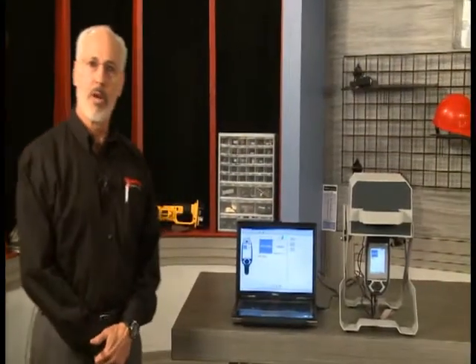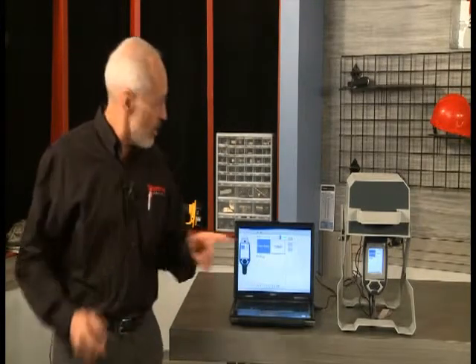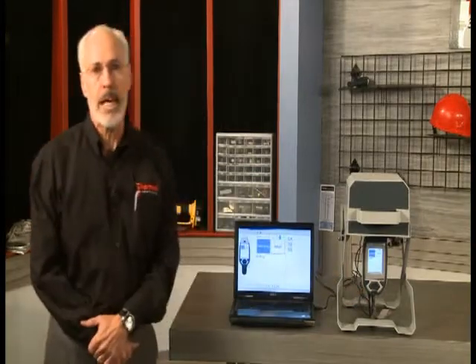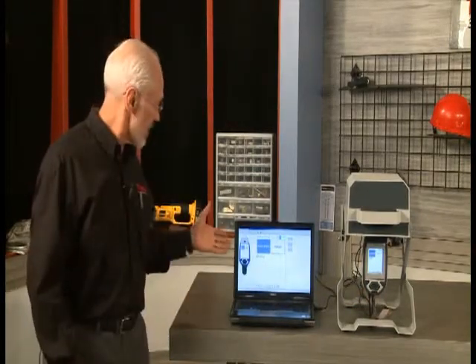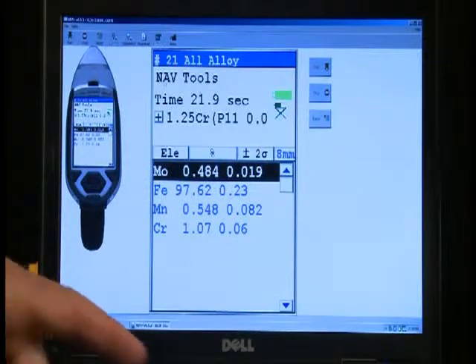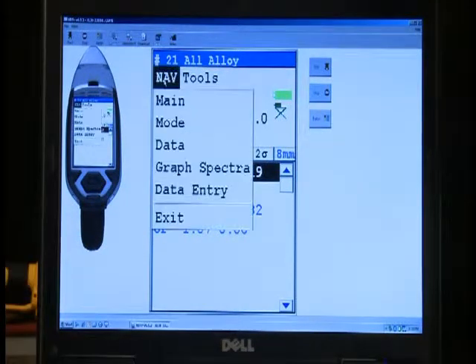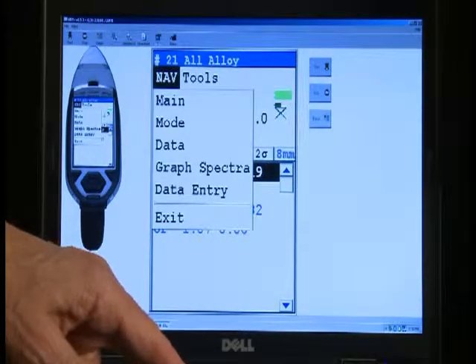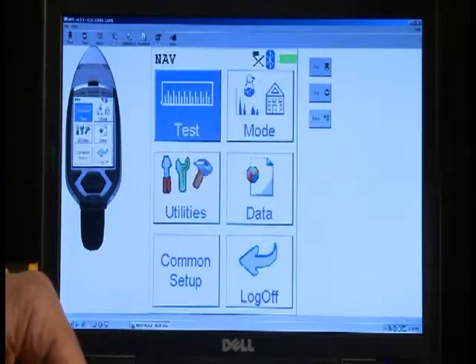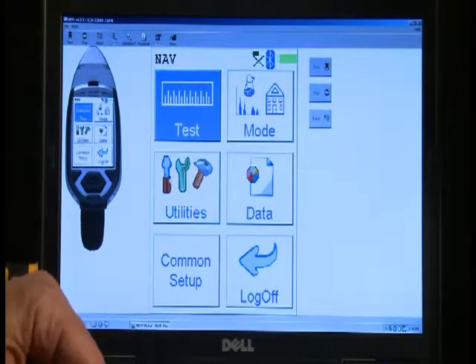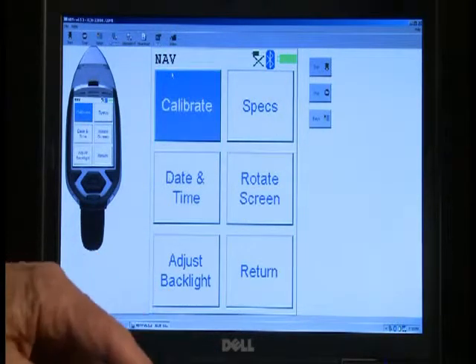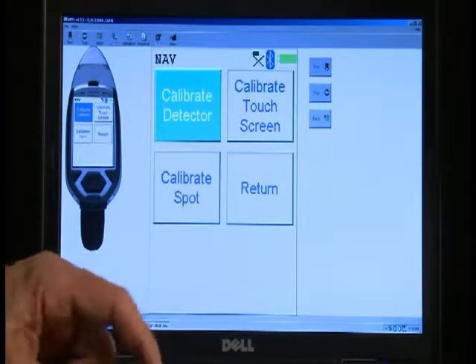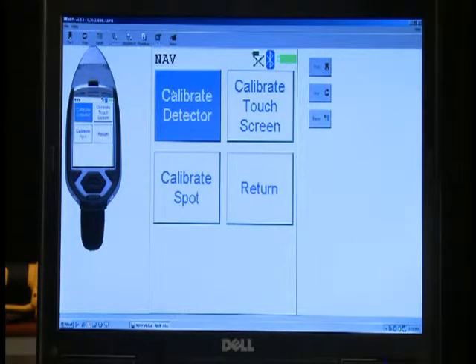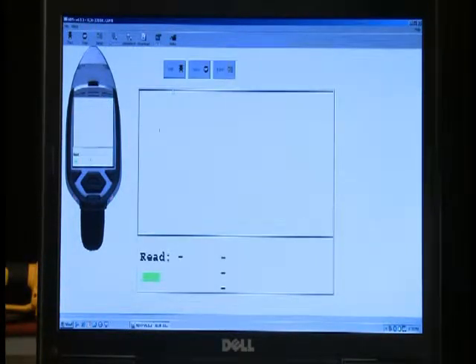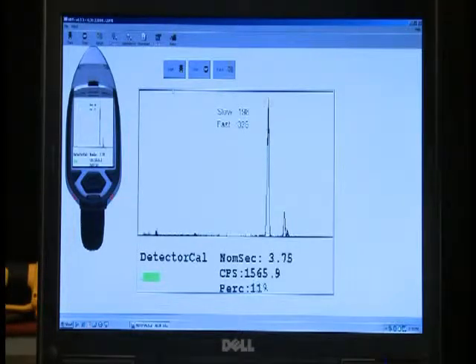This daily calibration will help prevent minor amounts of electronic drift from affecting your measurement results. Because we're hooked up via our USB cable, we'll perform and show the results on the PC, the personal computer. From the results screen, we select the nav drop-down menu. From the list of options here, we select the main menu and then Utilities. From the Utilities menu, we select Calibrate. From the Calibrate menu, we can select the Calibrate Detector option. This initiates an automated detector calibration update that will take up to several minutes. This depends on the configuration of your instrument.